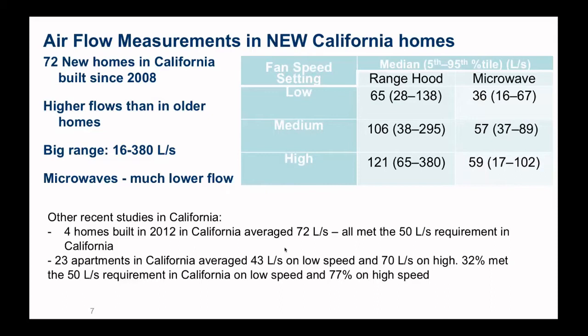This clearly shows changes in performance from laboratory tests to what you find in installations, primarily due to the airflow resistance of installed systems being much higher than the resistance used in laboratory testing.